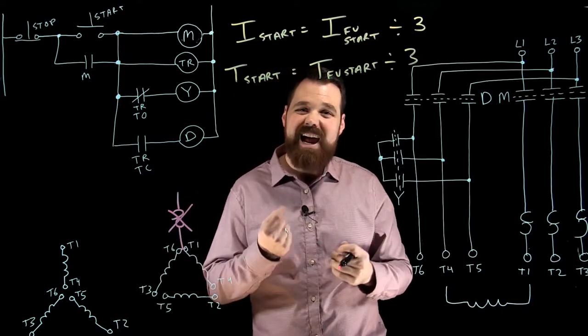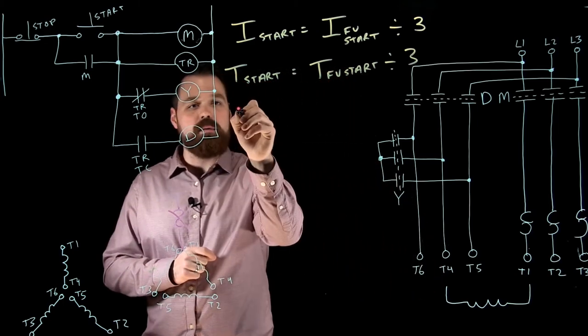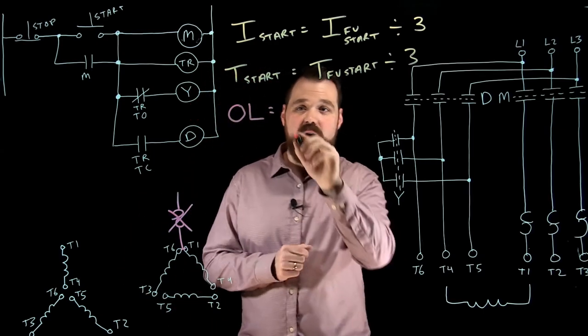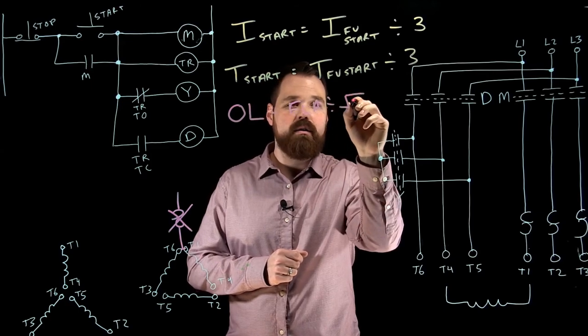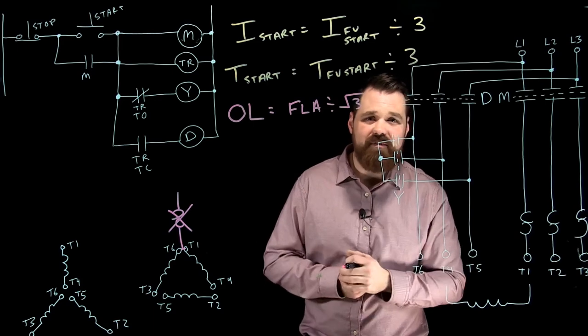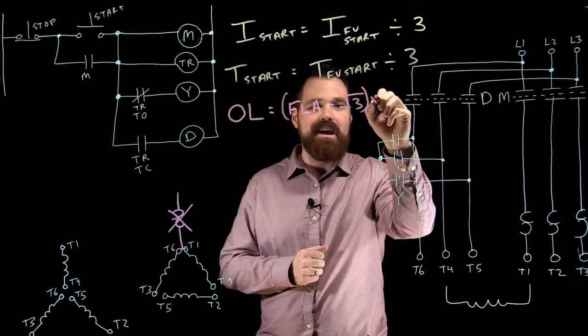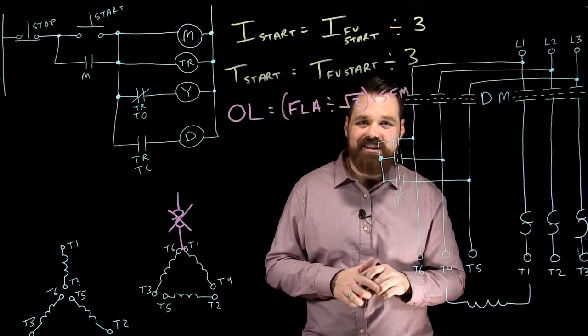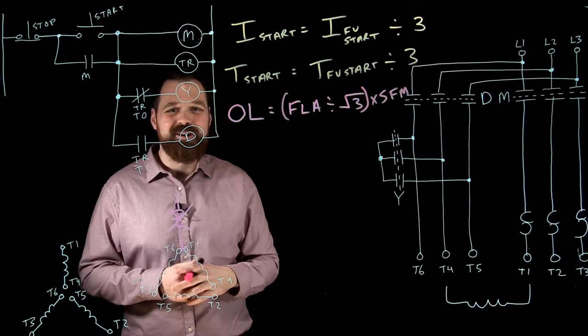In this case, our overloads have to be based off of phase current and not line current. So what we see when we're sizing our overloads is we are going to take our FLA, our full load current, divide it by root 3, because that's going to give us our phase current. You can also multiply it by 57%. So divide by root 3, and then we times it by our service factor multiplier, which we can find in the code book to size those overloads. Again, thanks for watching. I really hope this helped.